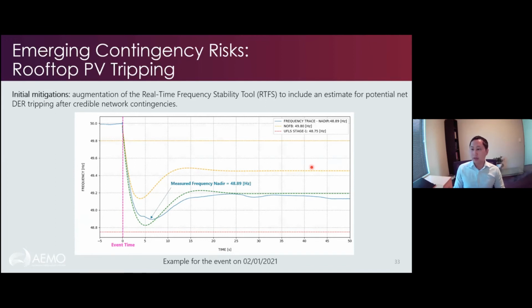So we had a frequency nadir of 48.89 hertz. So it was a pretty large deviation. This is UFLS stage 1. So we weren't too far off from UFLs. This is what we predicted based on just the network contingency. So we would have had enough reserves in place, and had that network contingency occurred by itself without that DER tripping, we would have got to this frequency. But actually what happened is we got to this frequency, and once we've adjusted the RTFS to include DER tripping, we do start seeing similar results to what we actually observed.